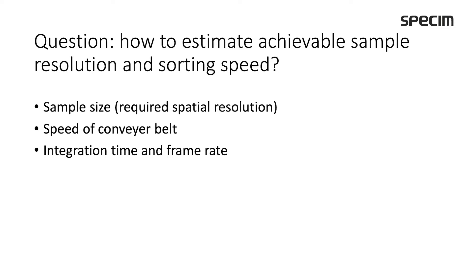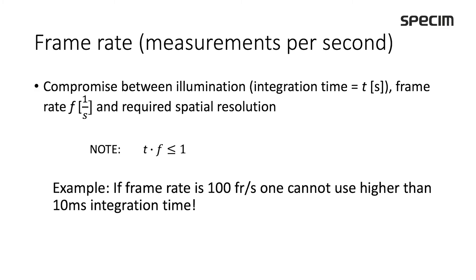We also need to understand the effect of integration time and frame rate. The frame rate means how many measurements we are doing per second, and it is important to understand that the integration time multiplied by the frame rate should always be one or less. Meaning, for example, if we have a frame rate of 100 frames per second, one cannot use a higher than 10 millisecond integration time.